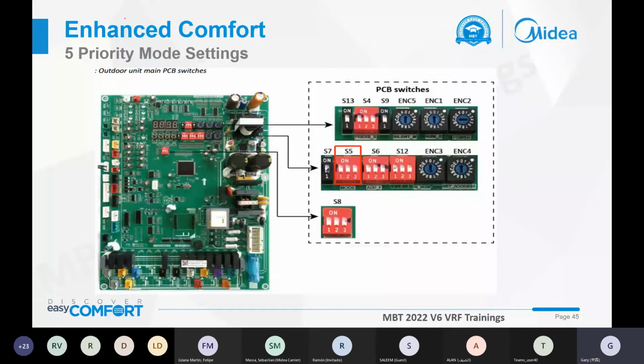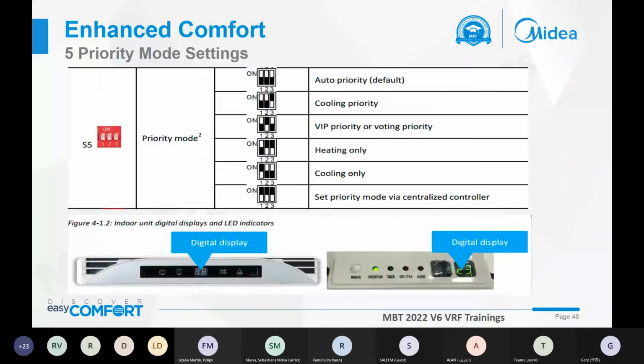We can set the priority mode from the S5 dial switch. We can have 5 different priority mode settings in total. We can also check the sequence in which modes flash on the indoor unit LEDs to see what priority mode is set in the outdoor unit from the indoor side.